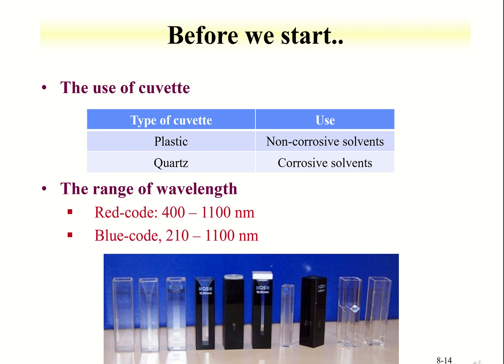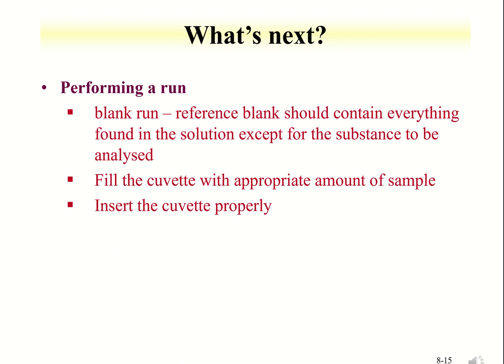Using the right cuvette is also important in the measurement of absorbance. The choice of using a cuvette depends on the medium in which your sample is dissolved in. Please request for a quartz cuvette from our lab technicians if your sample is dissolved in an organic solvent, such as alcohol. Otherwise, you may use a plastic cuvette which is readily available in the labs. There are also marks on the cuvette which indicate the range of wavelength which light can transmit through.